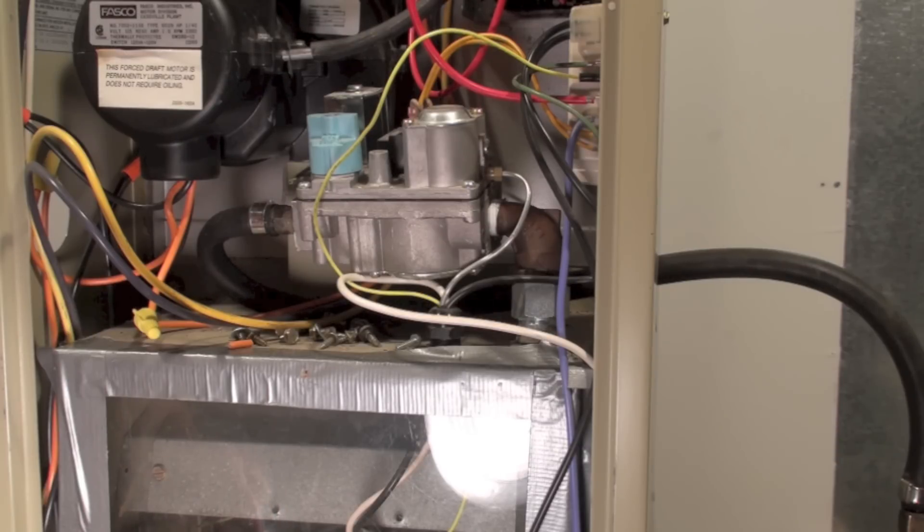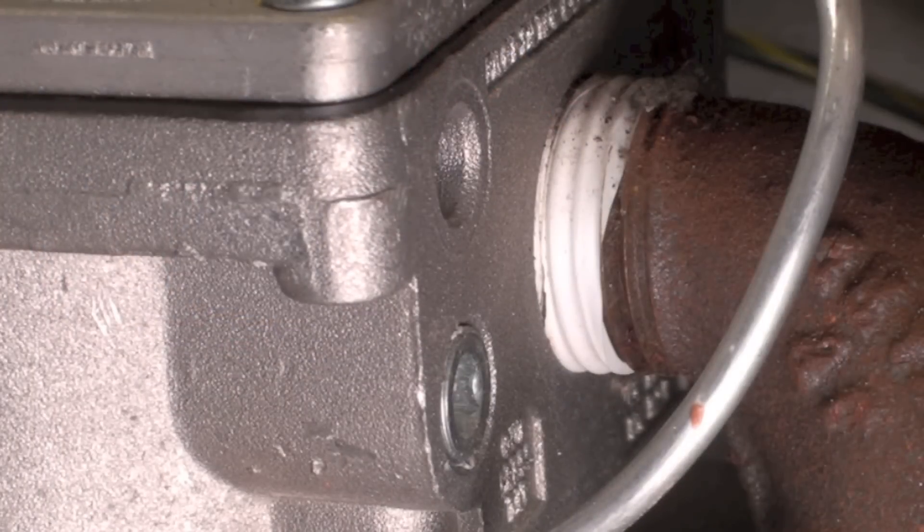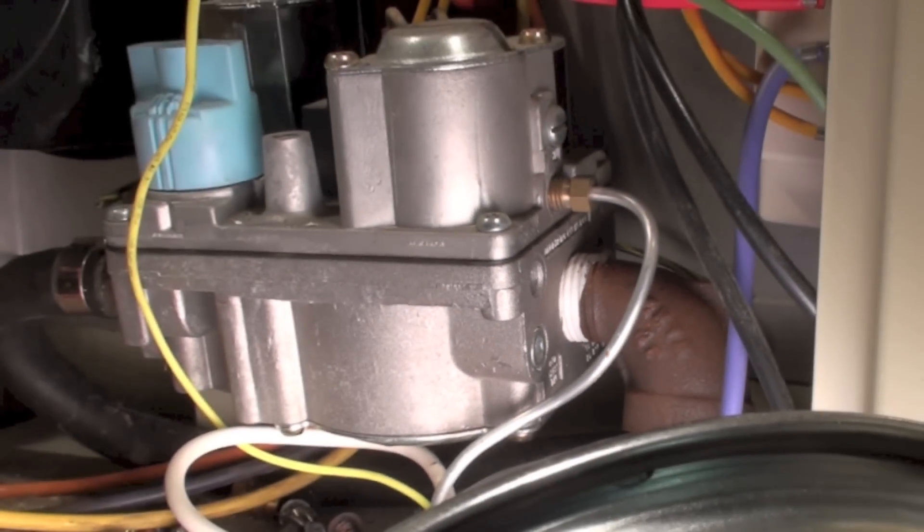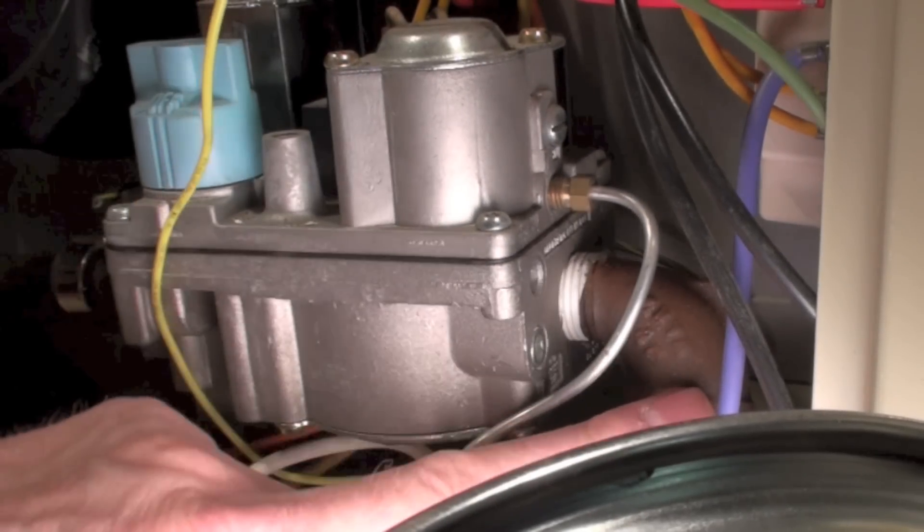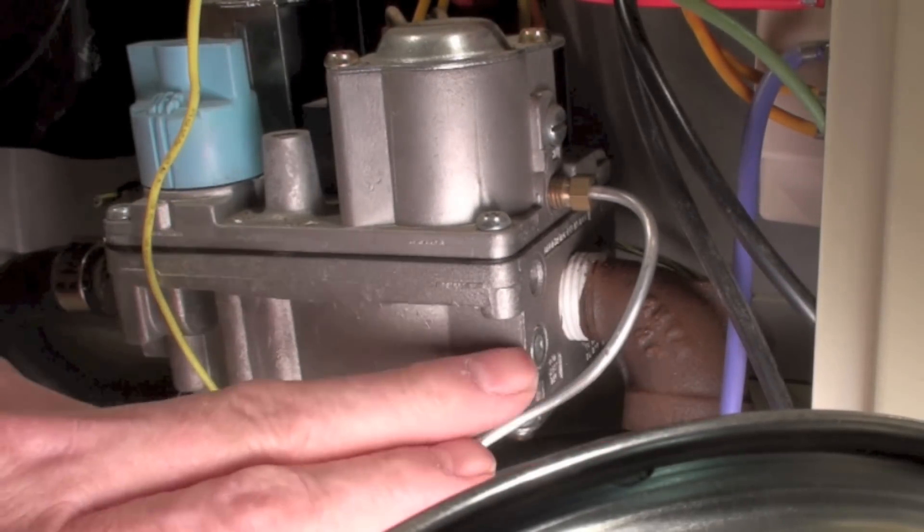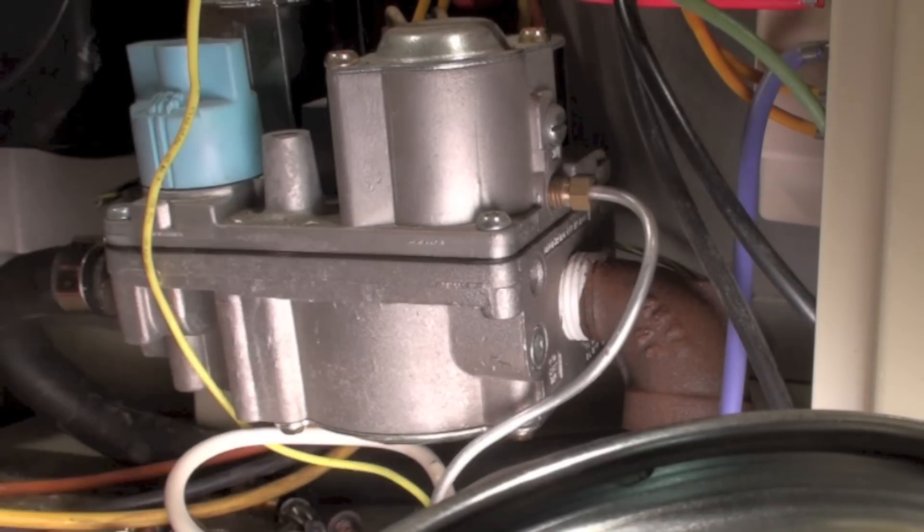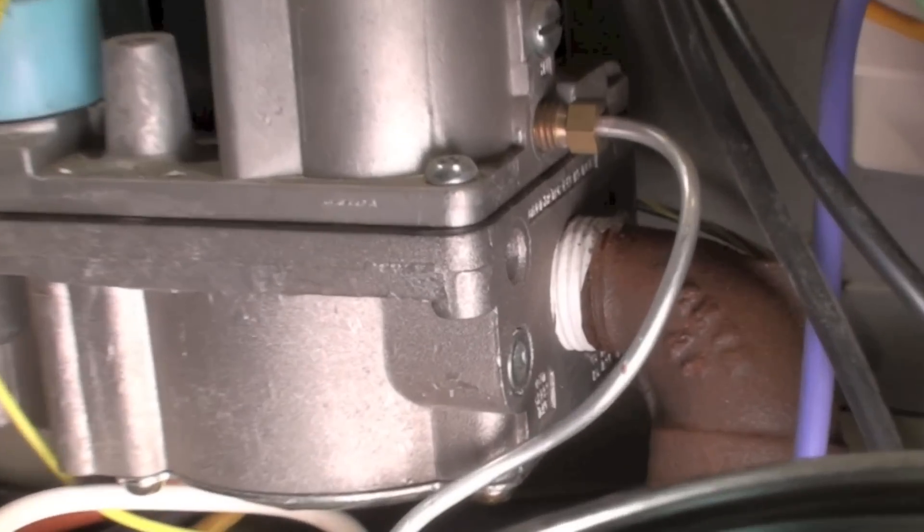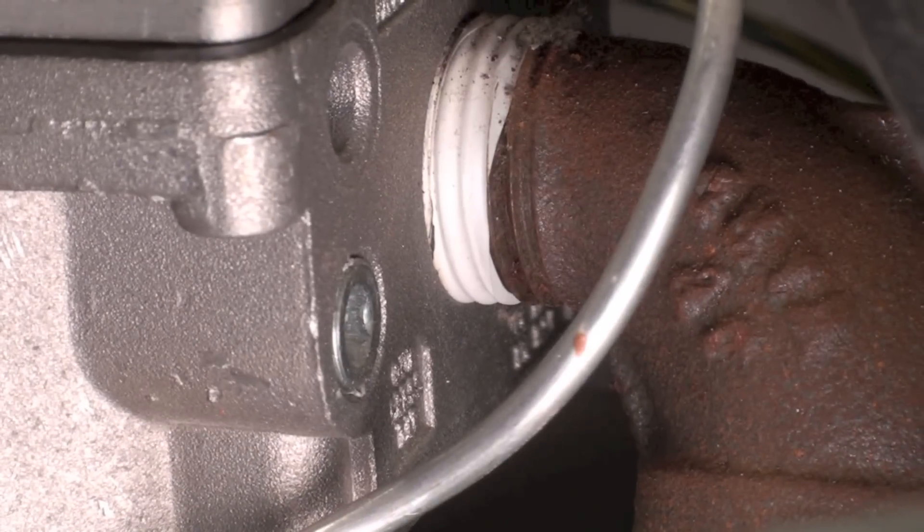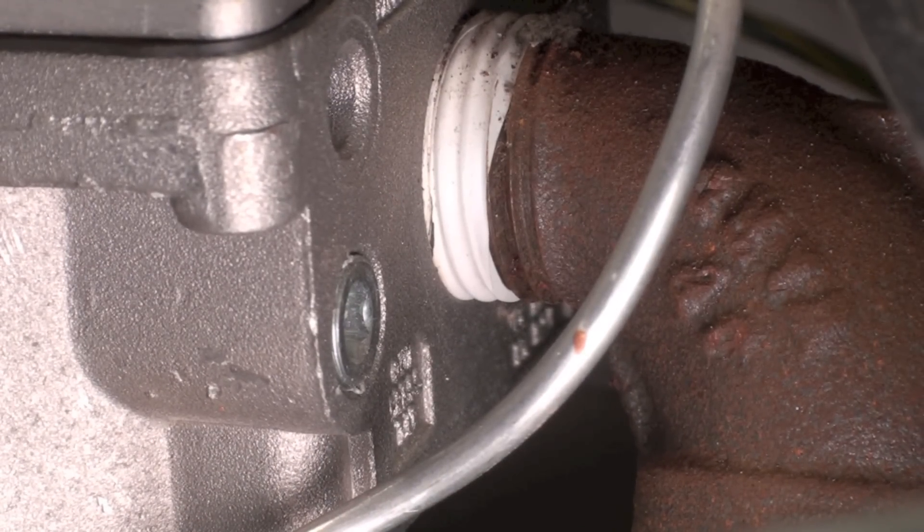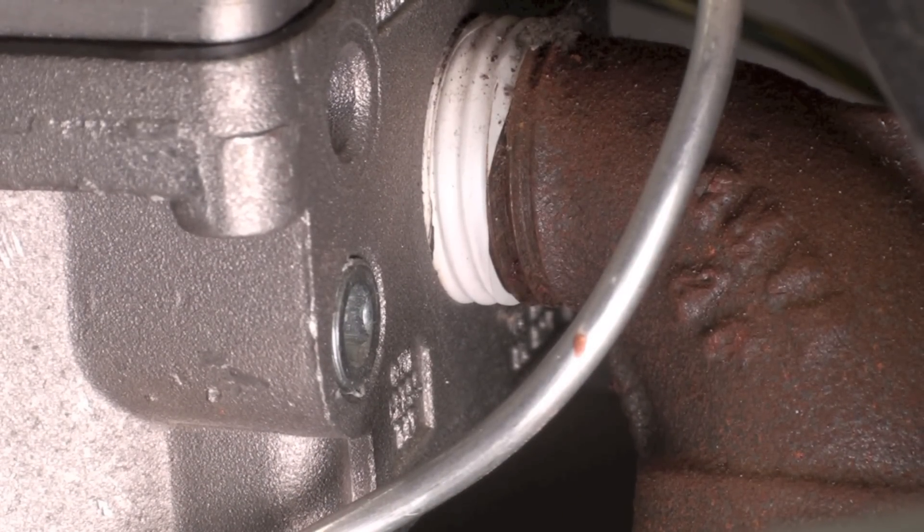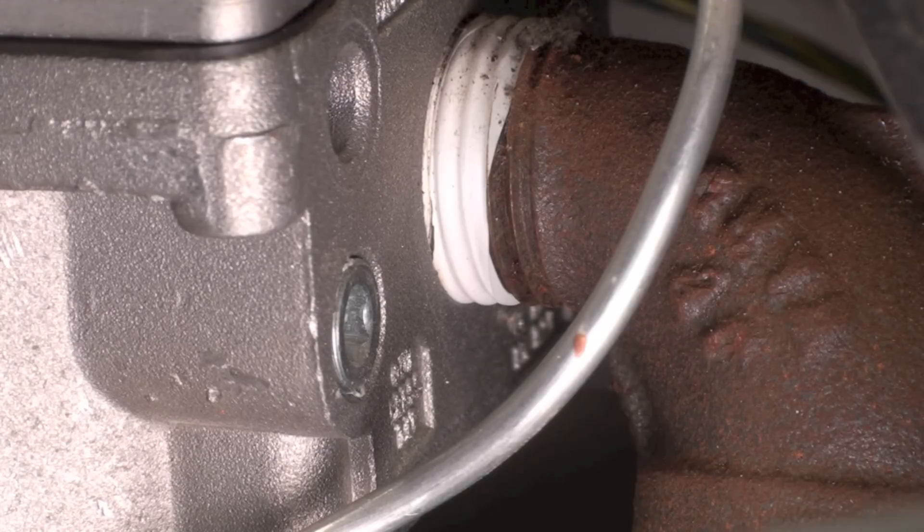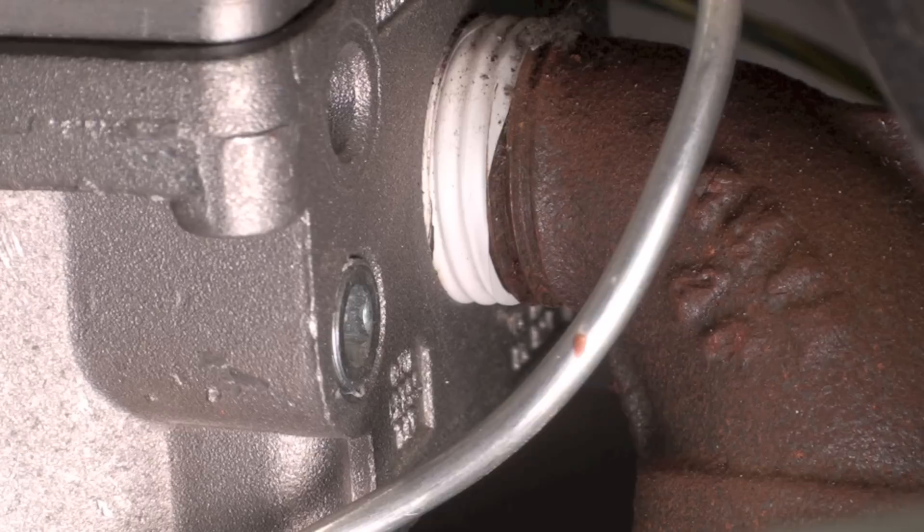Okay, here's the output of the valve. The tap's right here, it's fairly standard. First thing is shut down the furnace, turn off the gas cock, and we'll hook our tap onto there so we can get a manifold pressure.